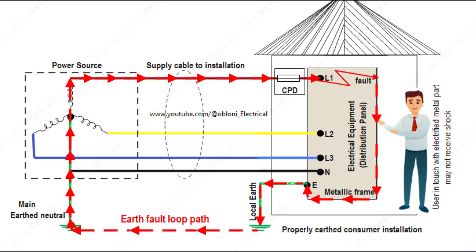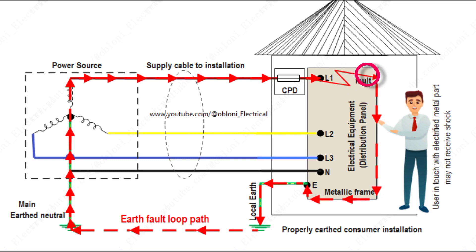Take note: in the TT system, the earth fault loop path includes the earth. That is why care must be taken to ensure that the earth electrode is properly connected to the earth, so that the impedance of the earth fault loop path will be very low. An earth fault loop path is the closed circuit that a fault current takes when there is a connection between a live conductor and earth, and in a TT system, the earth becomes part of that path.